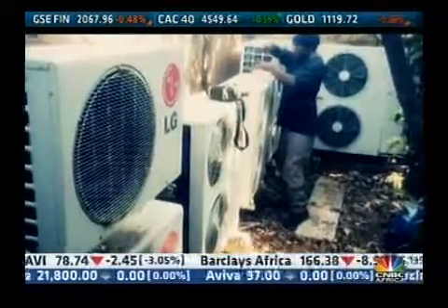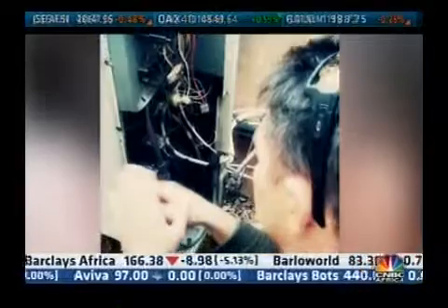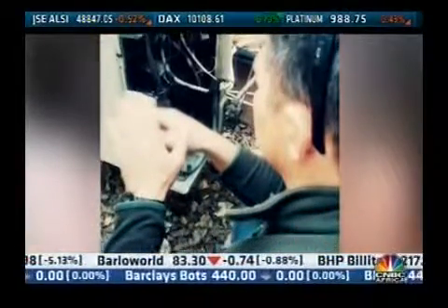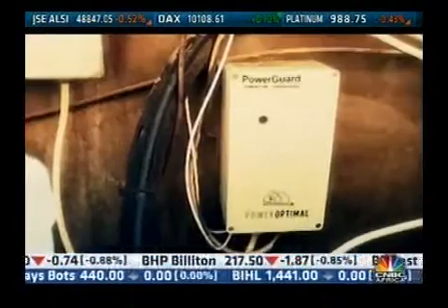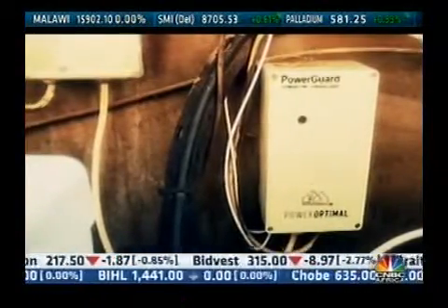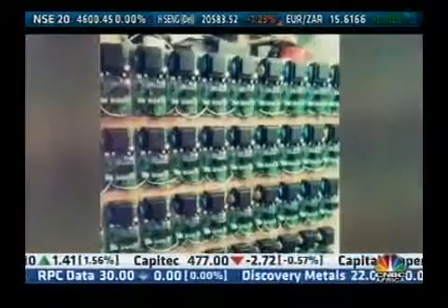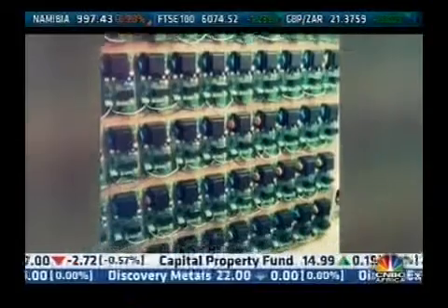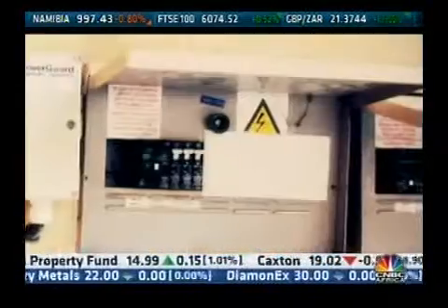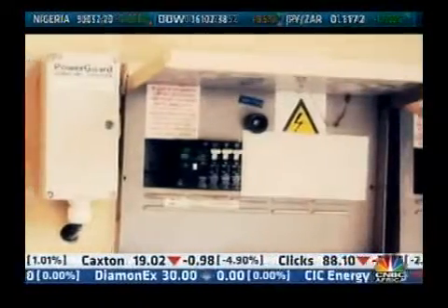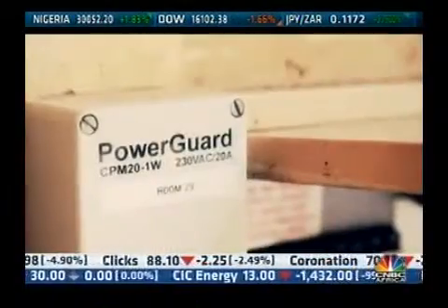So beforehand we would do an assessment of the site, and then we would decide which loads to manage together with the property owner or the manager at the property. And then we would only connect to those loads. But in terms of knowing where every load is, actually the system is in a way agnostic to that. It just broadcasts a general shed signal, and there's some intelligence built in. Each receiver has got a bit of fuzzy logic, so each load has got some intelligence built in to make its own decisions on when it will switch and for how long, and when it will switch back on again and so forth. Is anybody else in the world doing this?